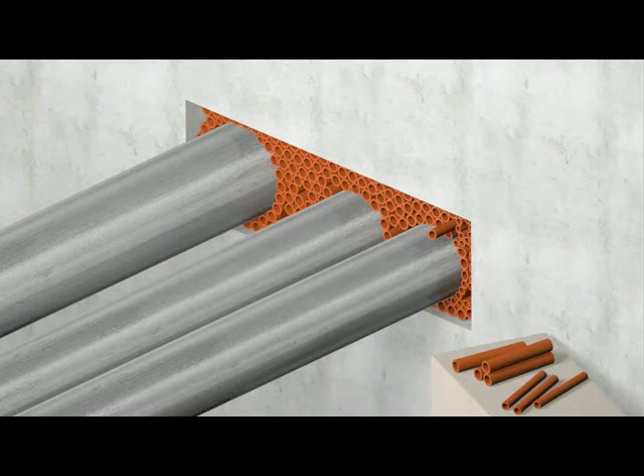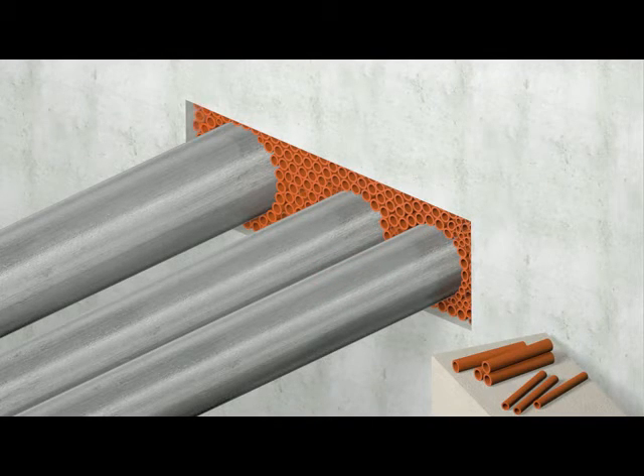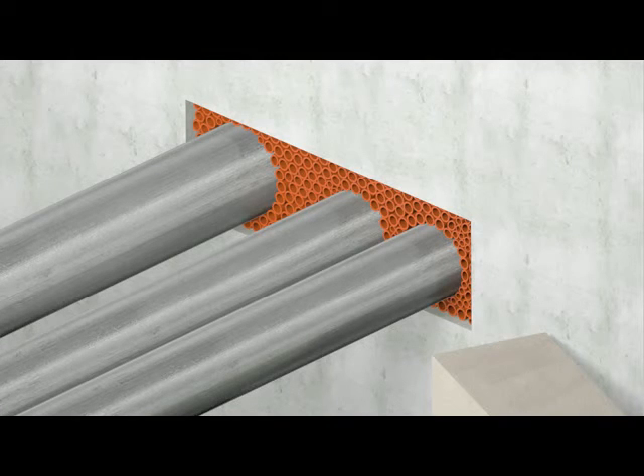At the final stage, to create a very tight fit of the whole set of fillers, the sleeves can be inserted with the help of flat nose pliers. A tight fit of the filling with filler sleeves is essential for the overall mechanical stability and the ultimate tightness ratings.